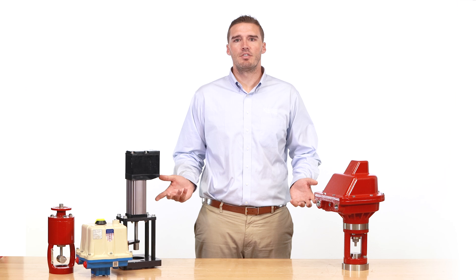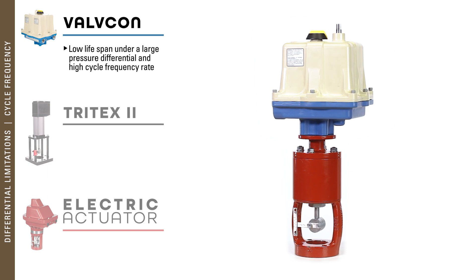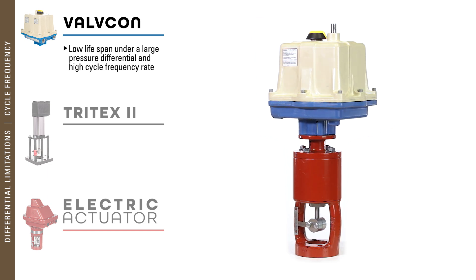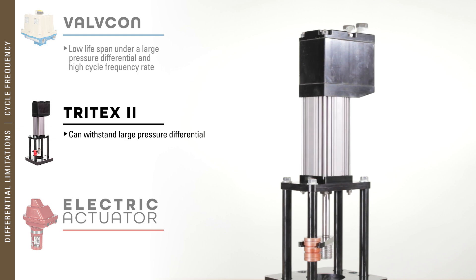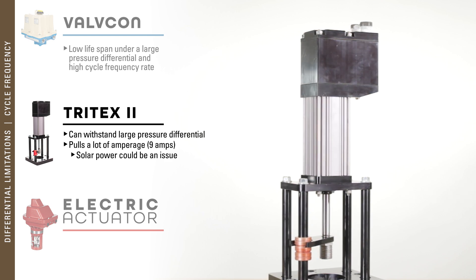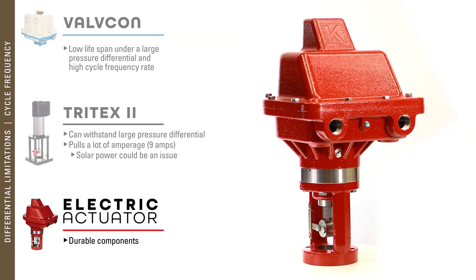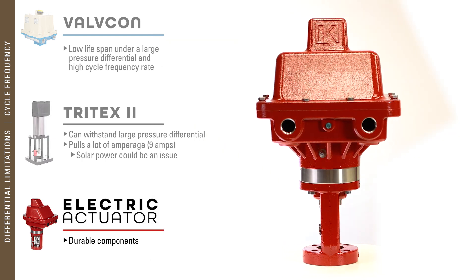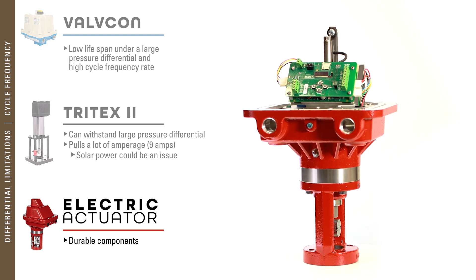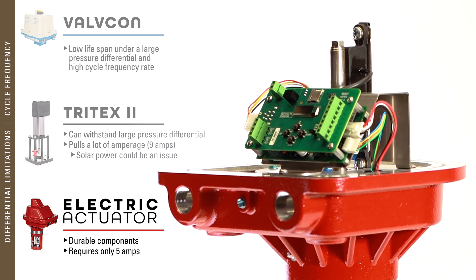These three actuators have differential limitations and cycle frequency considerations as well. The Valvcon lifespan under a large pressure differential and high cycle frequency is very low. The Tritex can stand up under a large pressure differential; however, it pulls a lot of amperage, meaning solar power could be an issue in certain regions. The Kimray electric actuator has overcome these challenges because it is built with durable components designed specifically for the modern oil field and because it only requires 5 amps.